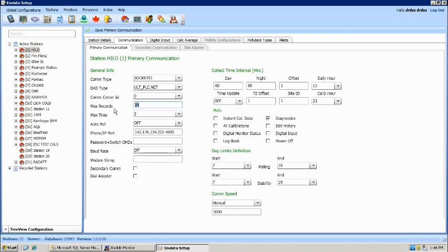And when you're getting that much data, you might still want to leave the comm speed at a slower setting to allow the data logger to have the time to compile its response and format it for transmission back to comm center. So for a very, very fast polling type of connection, I could even see this being a great setting. So 48 records with a slow comm speed, just so that everything has a chance to come back in.